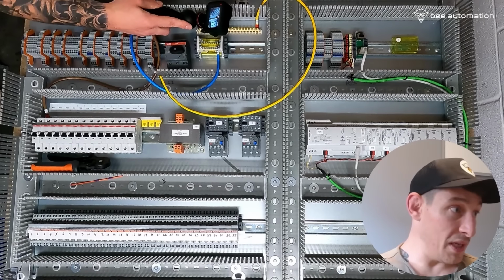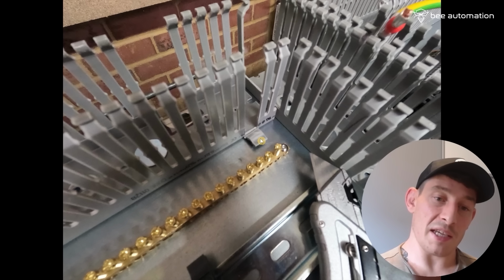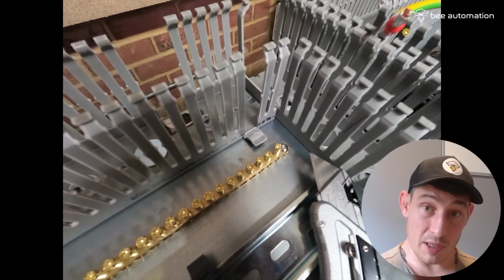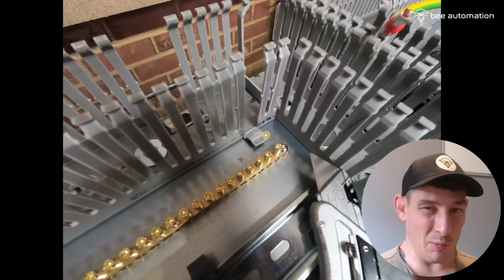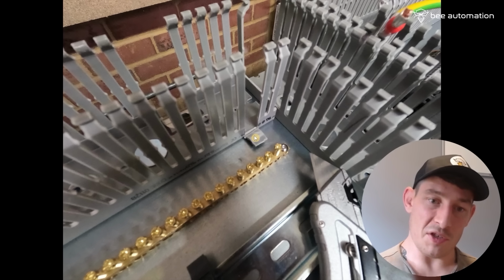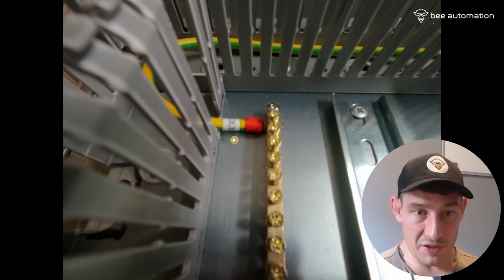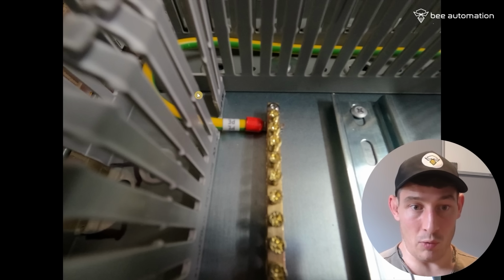Then terminating the neutral on the neutral bar side, and the protective earth on the earth bar side. You'll see here I'm cutting out a section of the finger trunking so the protective earth can go straight, flat, into this terminal block. Before it was bending and I didn't like it - it wasn't too bad, but I thought let's just cut a section out. Now it goes straight in rather than bending.